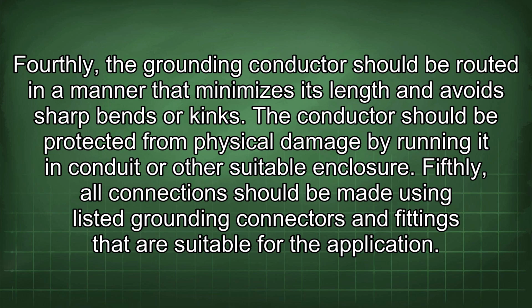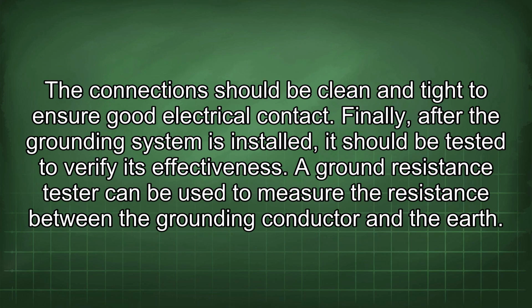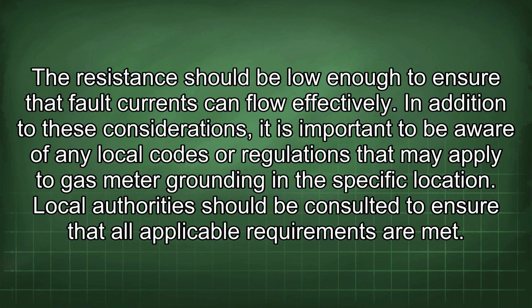Fifthly, all connections should be made using listed grounding connectors and fittings that are suitable for the application. The connections should be clean and tight to ensure good electrical contact. Finally, after the grounding system is installed, it should be tested to verify its effectiveness. A ground resistance tester can be used to measure the resistance between the grounding conductor and the earth. The resistance should be low enough to ensure that fault currents can flow effectively.